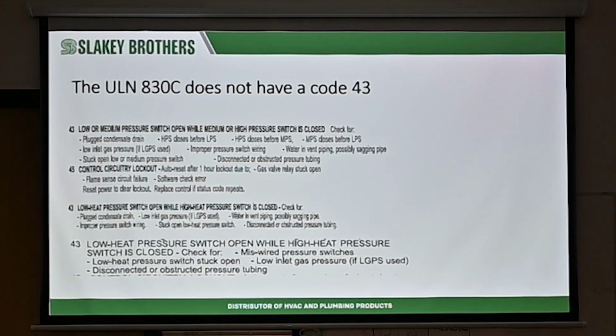So that's what you're looking at. The other thing you want to look at is you can bypass this, trick it to come on, or use the little T's that come with the UEI. So you put your little T in here, put the manometer there, a little short piece of pipe right in there, so don't forget. And the unit comes on, and the unit starts running. And then 5 minutes later, it turns off, where you can be watching your pressure.